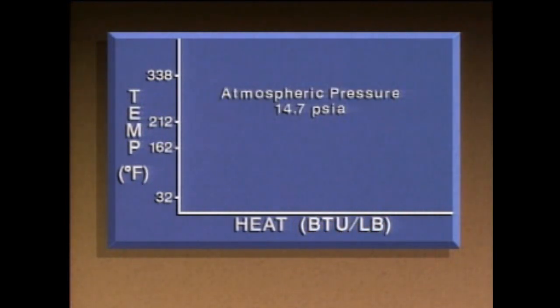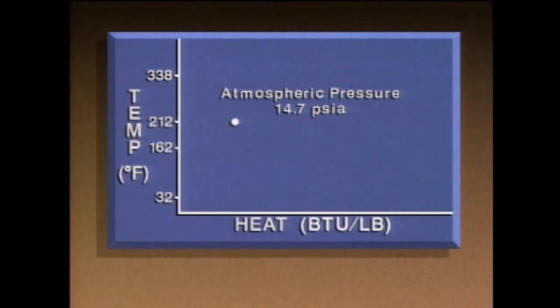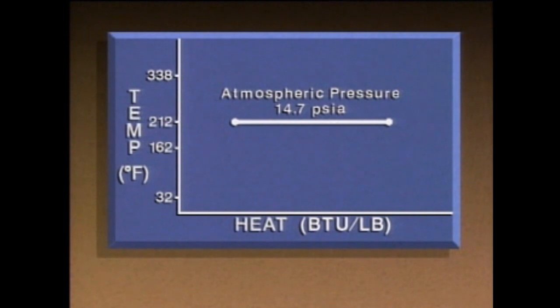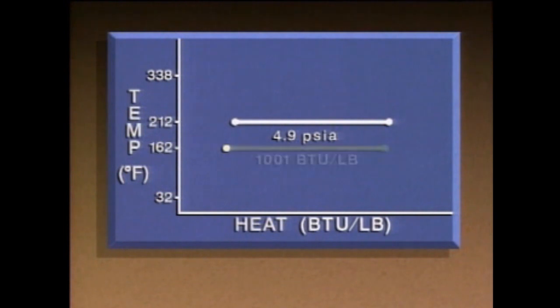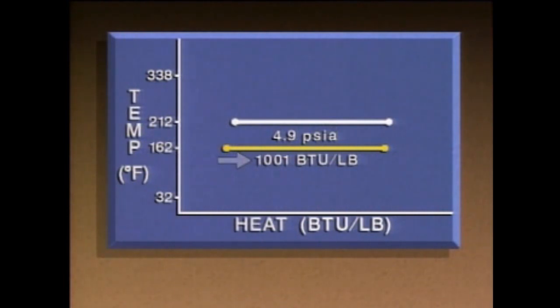Atmospheric pressure is 14.7 PSIA. At atmospheric pressure, water starts boiling at 212 degrees Fahrenheit. On our graph, this is the point at which water first starts boiling, and this is the point at which all the water is boiled into steam. This line represents the latent heat of vaporization. For one pound of water at atmospheric pressure, it takes about 970 BTUs of heat to boil all the water into steam. At a pressure of 4.9 PSIA, a pound of water boils at 162 degrees, and the latent heat of vaporization is around 1,001 BTUs per pound. So when the pressure is reduced, water boils at a lower temperature, but it takes more heat to boil all the water into steam.